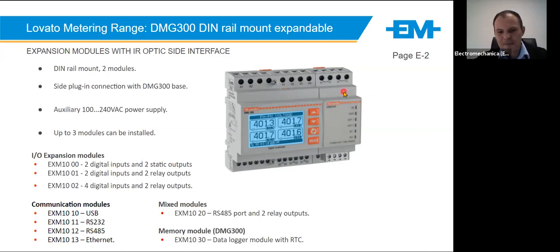Quite a nice feature. Plugging in the data logger with the real-time clock, you can go and say, trend this variable inside this meter. So volts, amps, kilowatts, kVAR, PF, at a specific interval, continuously trend. Then I can connect to this data log, and I can pull that off in a spreadsheet format. Or if I've had Synergy, the management system on top, go take that data log and present it back into the system. Okay. Again, that demand management function, which I showed on the other DMG, is available in these two.